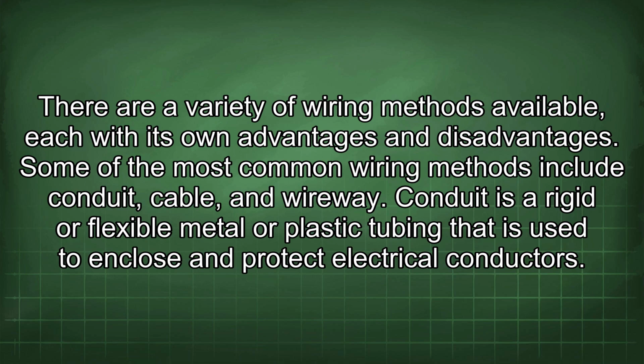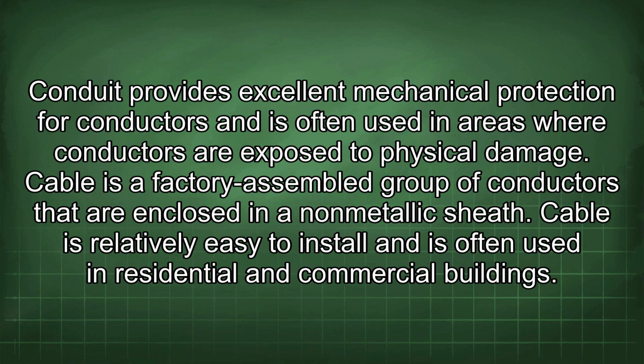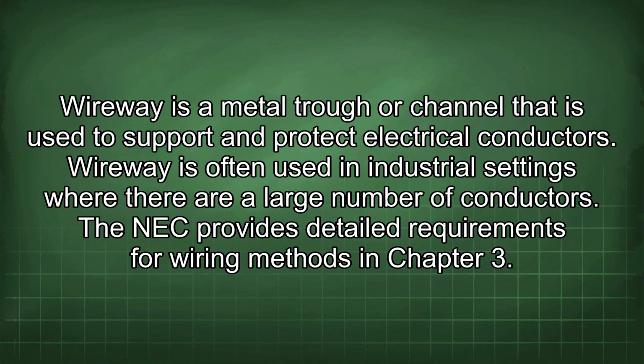Some of the most common wiring methods include conduit, cable, and wireway. Conduit is a rigid or flexible metal or plastic tubing that is used to enclose and protect electrical conductors. Conduit provides excellent mechanical protection for conductors and is often used in areas where conductors are exposed to physical damage. Cable is a factory-assembled group of conductors that are enclosed in a non-metallic sheath. Cable is relatively easy to install and is often used in residential and commercial buildings. Wireway is a metal trough or channel that is used to support and protect electrical conductors. Wireway is often used in industrial settings where there are a large number of conductors.